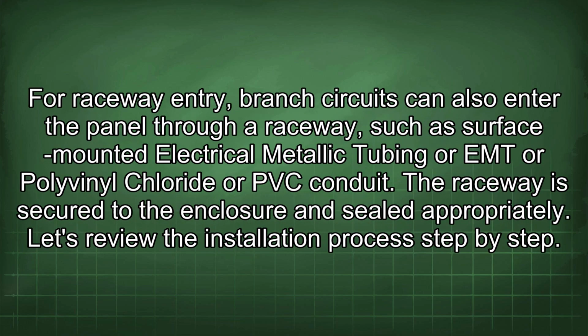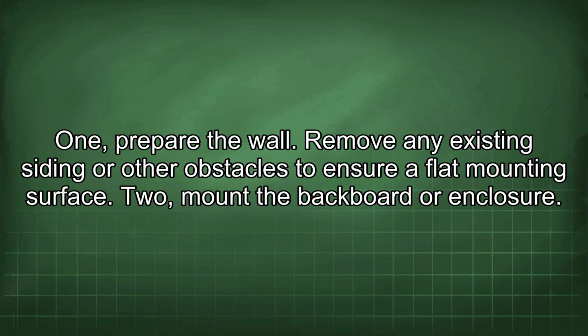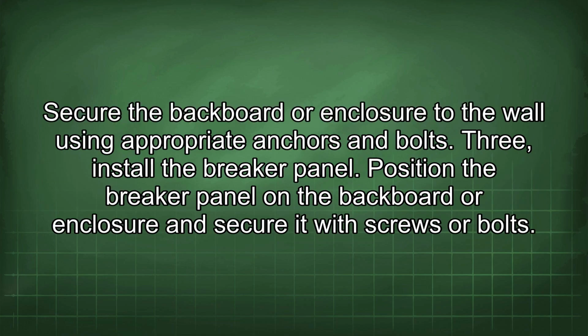For raceway entry, branch circuits can also enter the panel through a raceway, such as surface-mounted electrical metallic tubing or EMT or polyvinyl chloride or PVC conduit. The raceway is secured to the enclosure and sealed appropriately. Let's review the installation process step by step. 1. Prepare the wall. Remove any existing siding or other obstacles to ensure a flat mounting surface. 2. Mount the backboard or enclosure. Secure the backboard or enclosure to the wall using appropriate anchors and bolts.